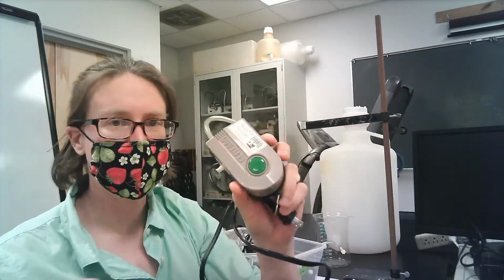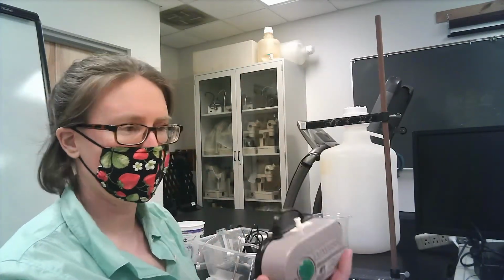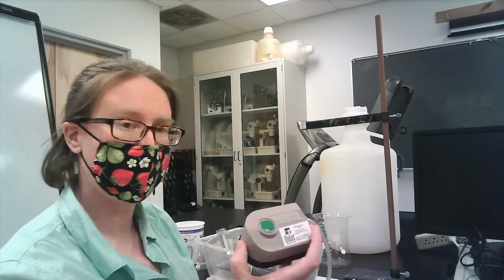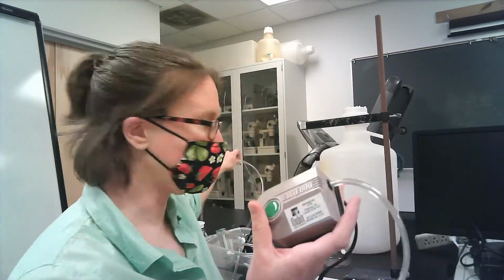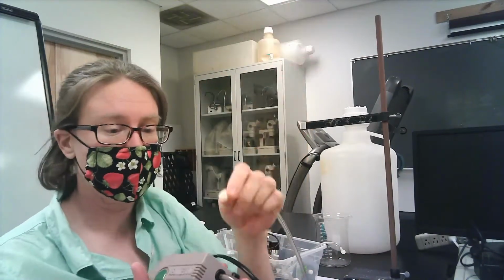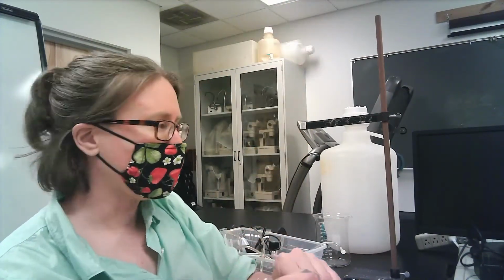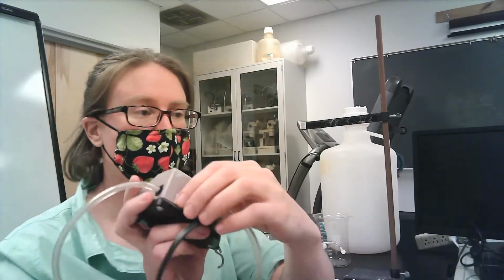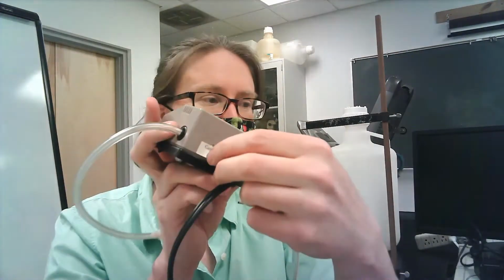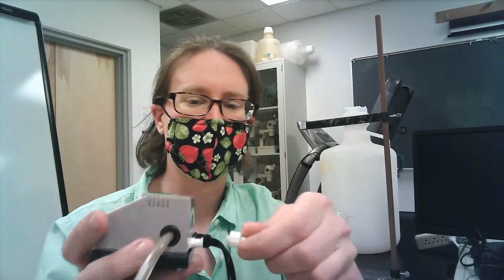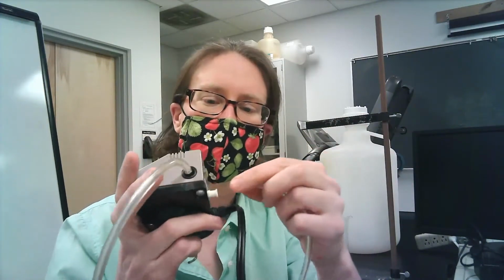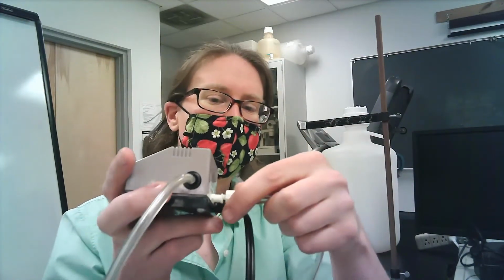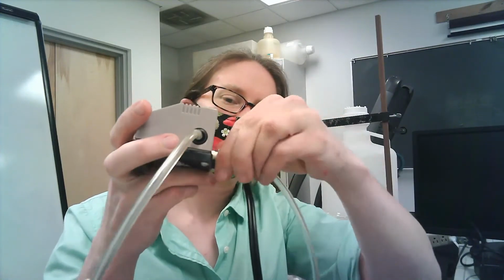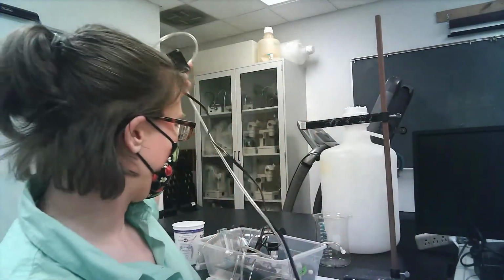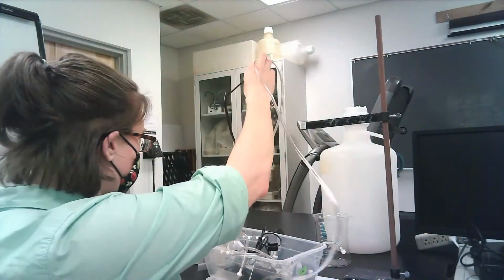Along with that, you'll find a gas pump in your kit. This gas pump is what's going to flow gas through our chamber. With the gas pump, there's a piece of very long tubing on your table. You want to collect that and connect that long tubing to the back of this gas pump. All these connections between these different pieces are called a Luer lock system, very similar to what's used for syringes. These pieces will just twist together to connect. So that's going to be your gas pump, and that's going to flow the gas through.